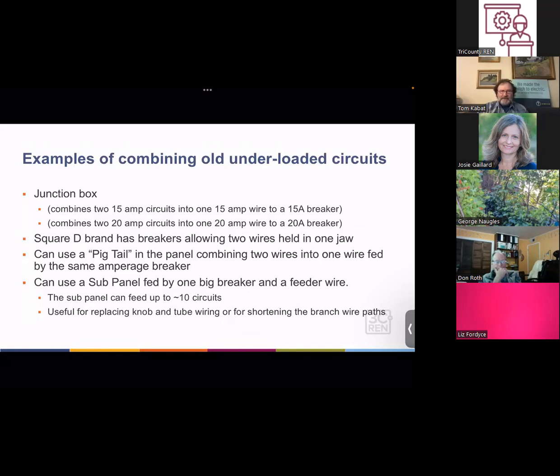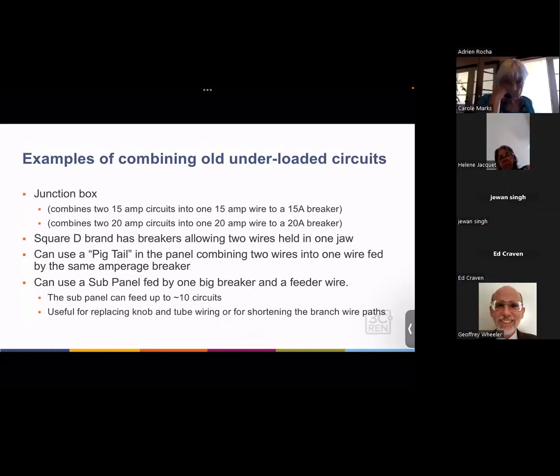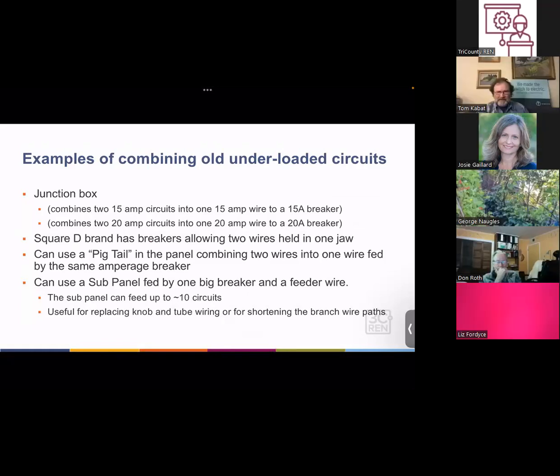Now some examples of combining old underloaded circuits. Since we've switched to LED lighting, we may have underloaded circuits. You could use a junction box to combine two 15 amp circuits into one 15 amp wire going to one 15 amp breaker. You need to keep using the same size breaker to protect those wires — you would not put two 15 amp circuits on a 20 amp breaker, since that wouldn't protect either circuit. The breaker needs to match the lower size of the wire.